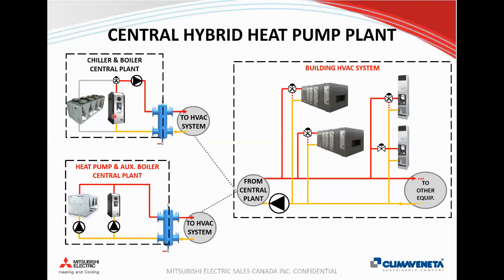So if we have a typical two-pipe changeover system and we have a reversible heat pump that is a chiller, but it can also provide heating, then the idea with this type of equipment is let's use that and try to use it as much of the season as we can during the shoulder season and for milder days in winter in heating mode. We'll get into this in the next slide, but because the heat pump will have a fixed cutout temperature, in most climates in Canada, you'll almost always need an auxiliary boiler, but this can provide resiliency and redundancy for your building. So really it's about using the heat pump for as much of the time as possible and supplementing with a gas or electric backup boiler as required, and maybe just on those peak days.